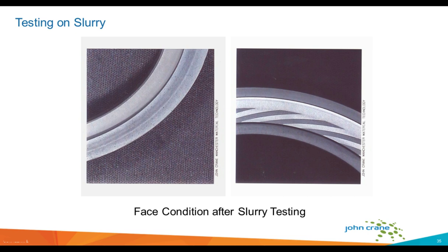On post-test inspection, you can see very clean and clear seal faces after this test running on a very abrasive slurry. So no adverse effects to the seal, and again, a good representation of the capability of this dynamic lift technology.